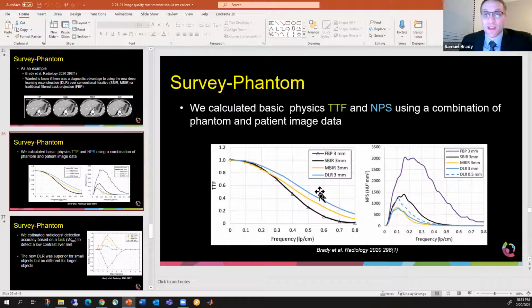For a national survey, I would do it as a function of accreditation. So maybe every couple of years. For example, in the US, we do it every 3 years. So in Thailand, maybe you could do it every 2 or 3 years. I would do it at the exact same cycle that you set up your DRLs. In my next talk, we're going to talk about measuring and collecting the dose data and submitting it to establish DRLs. And the IAEA typically says you should do it at least every 5 years. So you could probably do the image quality assessment at the same time as you do the dose.